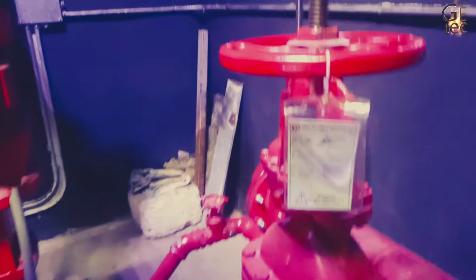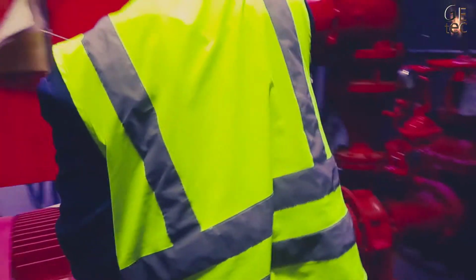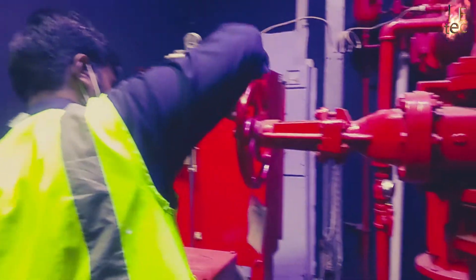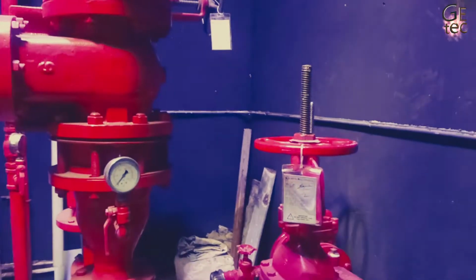This usually occurs if the building is very tall, such as in high-rise buildings, or in systems that require a relatively high terminal pressure at the fire sprinkler in order to provide a large volume of water, such as in storage warehouses. Fire pumps are also needed if fire protection water supply is provided from a ground-level water storage tank. Types of pumps used for fire service include horizontal split case, vertical split case, vertical inline, vertical turbine, and end suction.